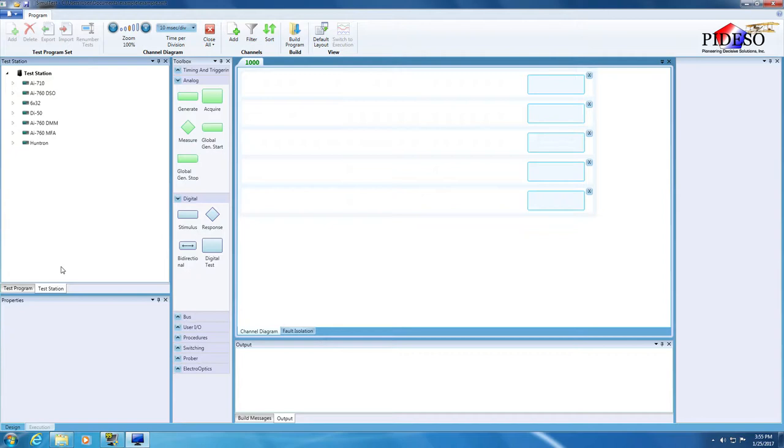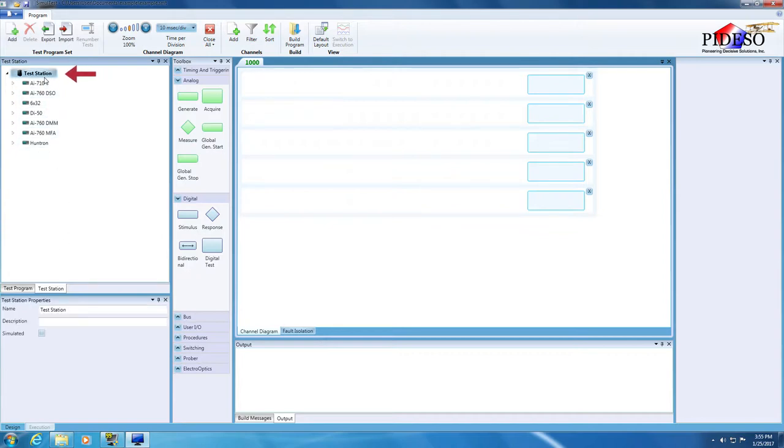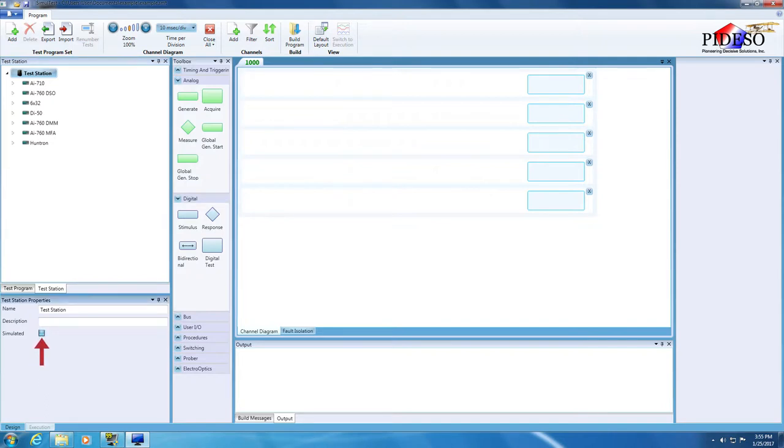Before we add an instrument to the test, note that if the instruments are not physically present on the system, you will need to develop the TPS in simulation mode. This is done by first clicking on Test Station, followed by checking the simulated checkbox here in the Test Station Properties pane.